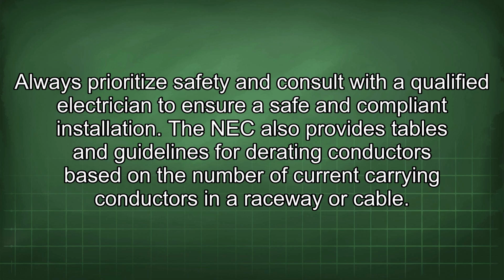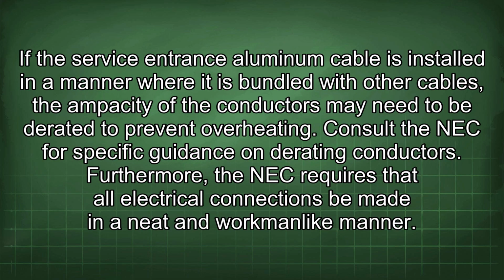The NEC also provides tables and guidelines for derating conductors based on the number of current carrying conductors in a raceway or cable. If the service entrance aluminum cable is installed in a manner where it is bundled with other cables, the ampacity of the conductors may need to be derated to prevent overheating. Consult the NEC for specific guidance on derating conductors.